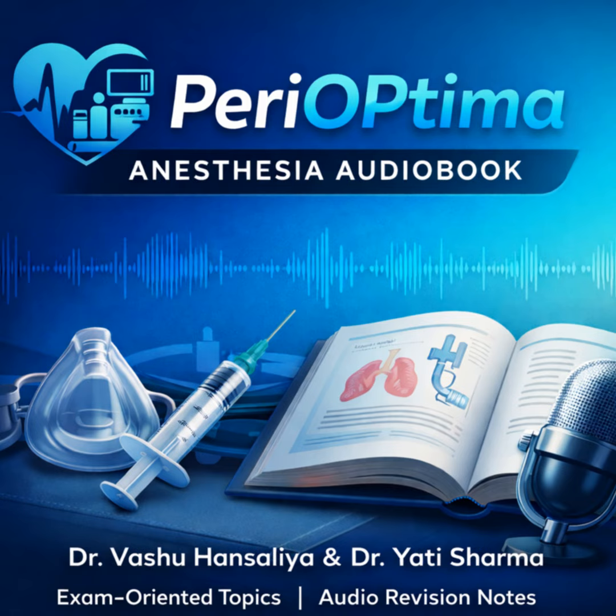What's the second test? The occlusion test, or compression test. You occlude the patient end of the circuit, close the APL valve, and pressurize the bag. It should hold pressure. Then when you quickly release the occlusion at the patient end, you should feel a vigorous blast of gas escaping, confirming flow through the whole circuit. If it's kinked, the bag will be impossible to squeeze.